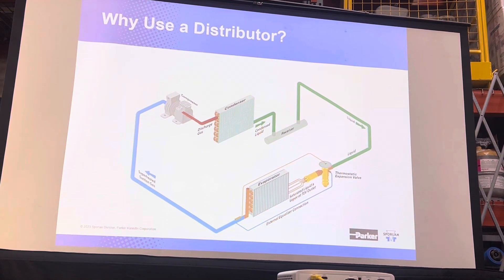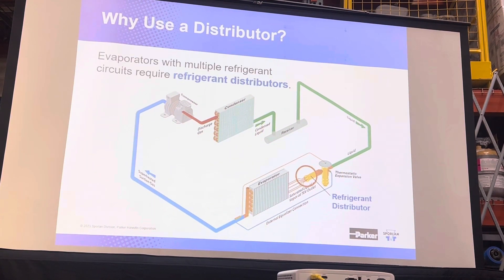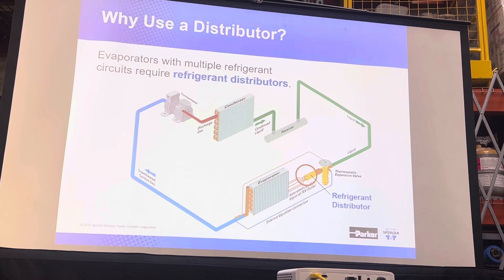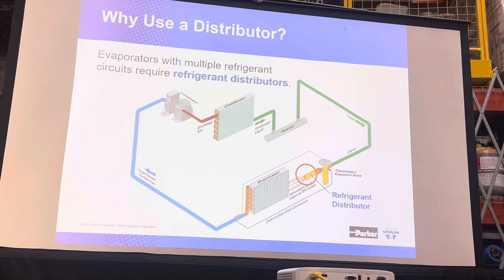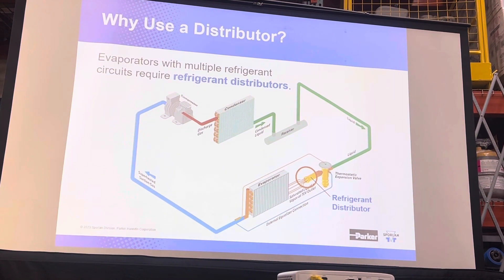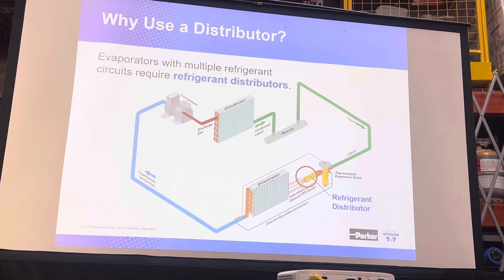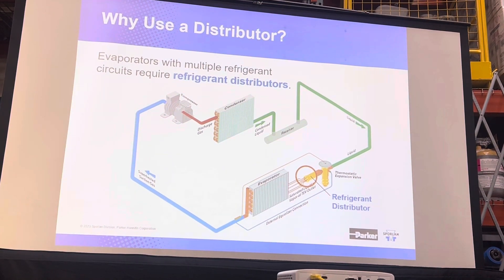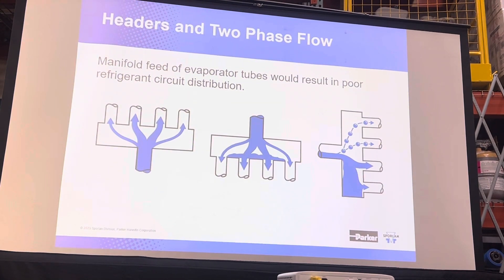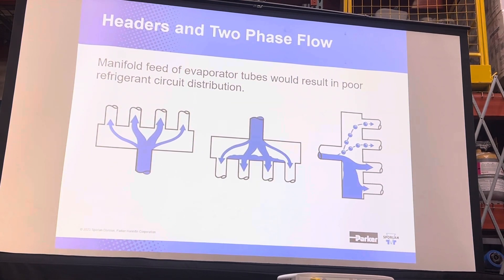Why is that important? Because as we leave the expansion device, we generally have saturated flow that is liquid and vapor — so you've got two-phase flow. Vapor wants to go one place, liquid wants to go another, and the distributor helps to mitigate the problems associated with that.